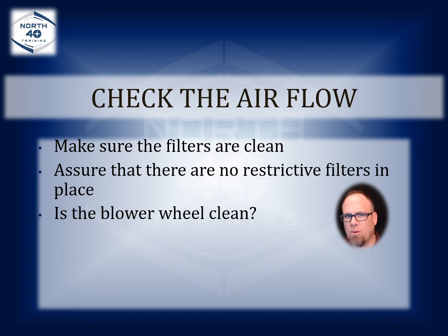Is the blower wheel clean? Now, ASHRAE and Energy Star both place a number on the percentage of decrease in airflow on the return side or the supply side as to whether or not it's going to affect the rest of the system. And that's 10%. A 10% restriction on either the supply side or the return side, both can be affected by the blower wheel, can affect the overall efficiency and capacity by up to 50%. That is so huge and such an easy thing to fix and to cure as well.